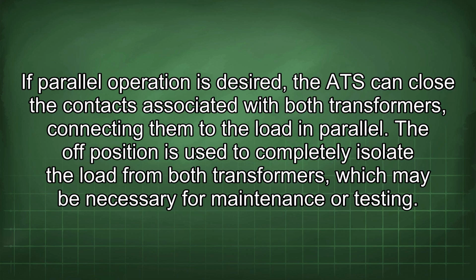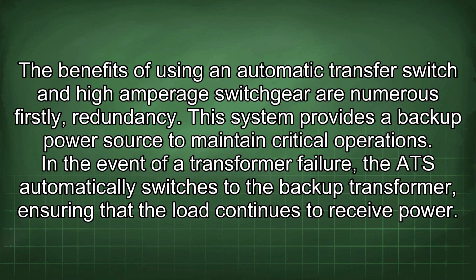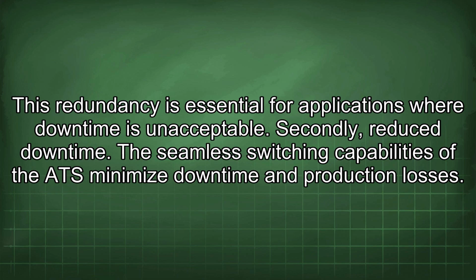The benefits of using an automatic transfer switch and high amperage switchgear are numerous. Firstly, redundancy. This system provides a backup power source to maintain critical operations. In the event of a transformer failure, the ATS automatically switches to the backup transformer, ensuring that the load continues to receive power. This redundancy is essential for applications where downtime is unacceptable.